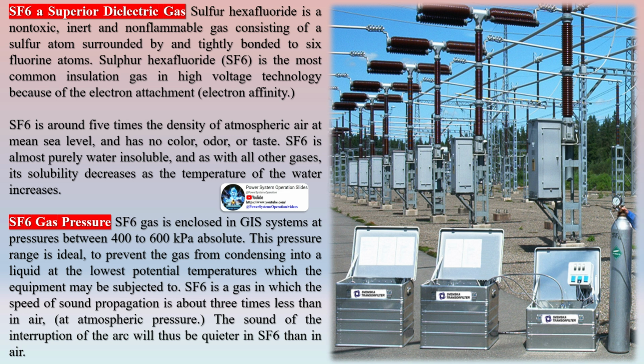Sulfur hexafluoride is a non-toxic, inert and non-flammable gas consisting of a sulfur atom surrounded by and tightly bonded to 6 fluorine atoms. Sulfur hexafluoride, SF6, is the most common insulation gas in high-voltage technology because of its electron affinity. SF6 is around 5 times the density of atmospheric air at mean sea level, and has no color, odor, or taste. SF6 is almost purely water insoluble, and as with all other gases, its solubility decreases as the temperature of the water increases.